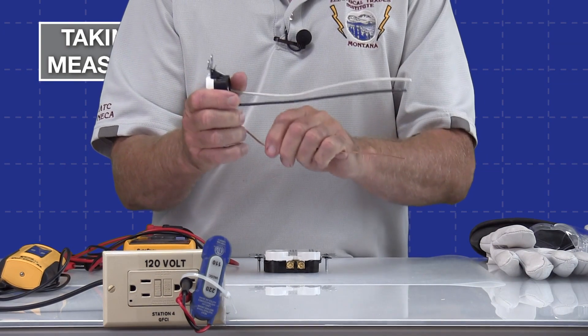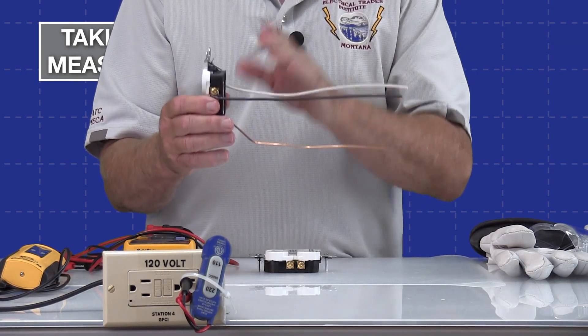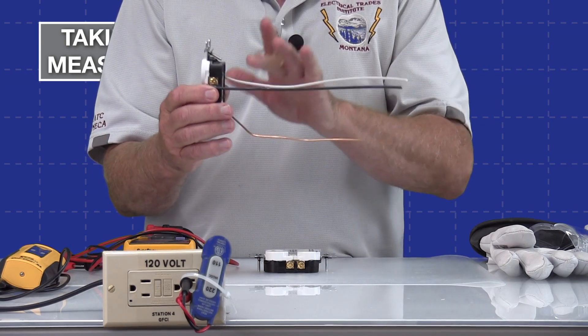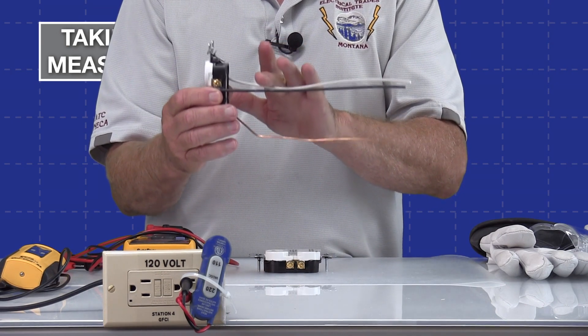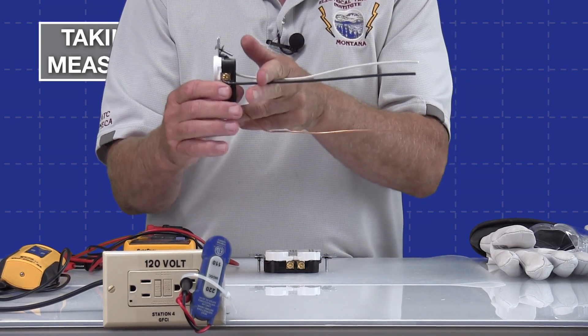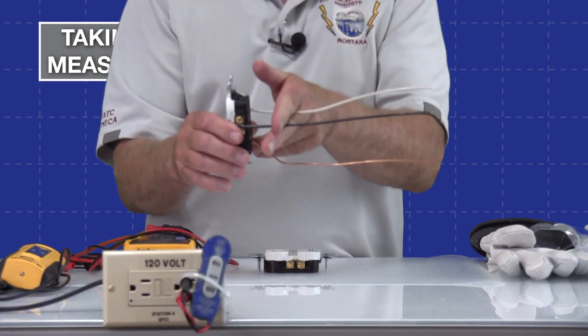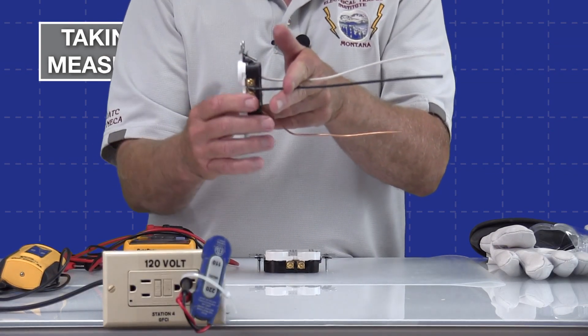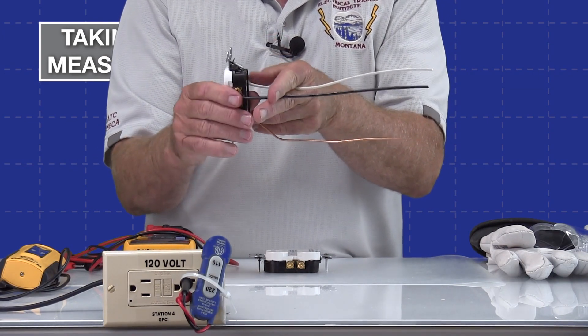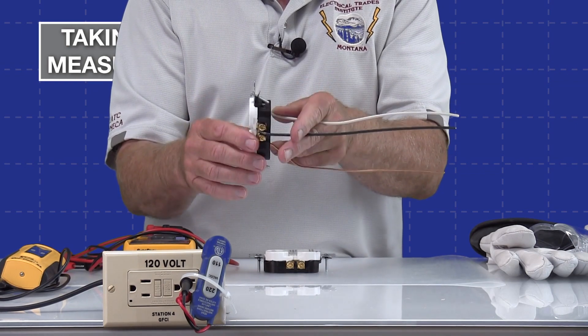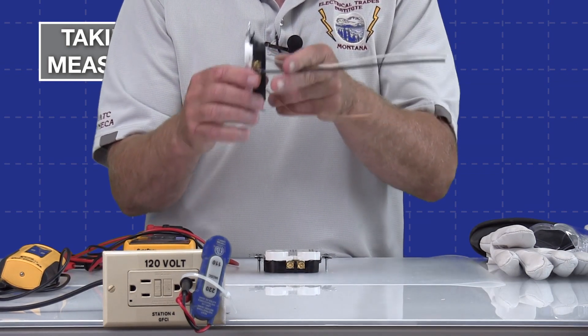As far as a GFCI receptacle, the way they work, they monitor between the ungrounded conductor and the grounded conductor, the hot and the neutral wire, and they look for an imbalance. There's a sensor inside the GFCI that's basically monitoring these two wires. If it sees an imbalance, in other words, if the black wire had one ampere on it, you need to have close to one ampere on the white wire or it trips.